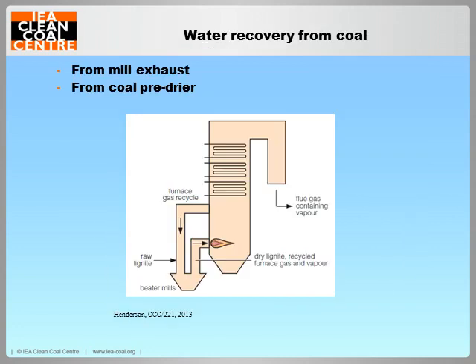Right, I now look at water recovery from coal. Drying the coal before it is combusted and recovering the moisture could provide water for internal use. Lignites, for example, can have inherent moisture contents as high as 70%. In conventional power plants, the drying takes place within the mill, as shown in this figure.